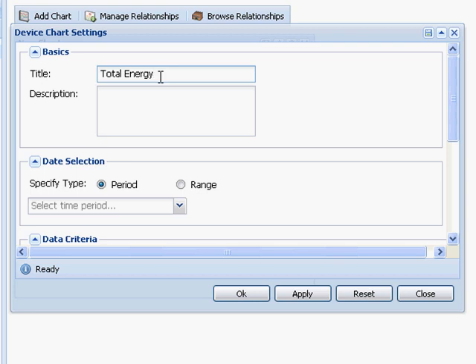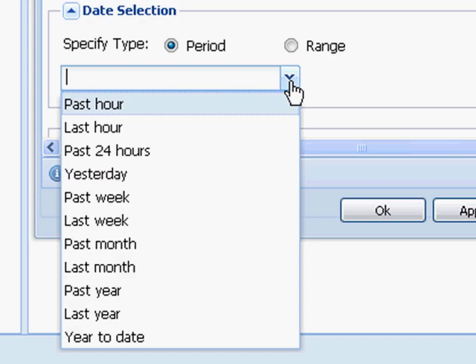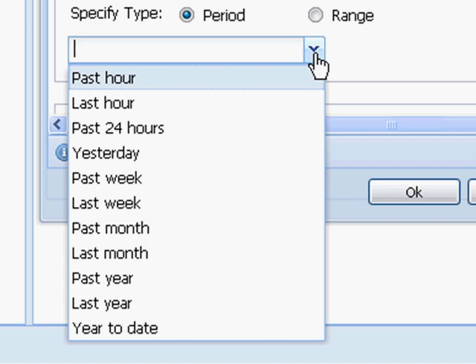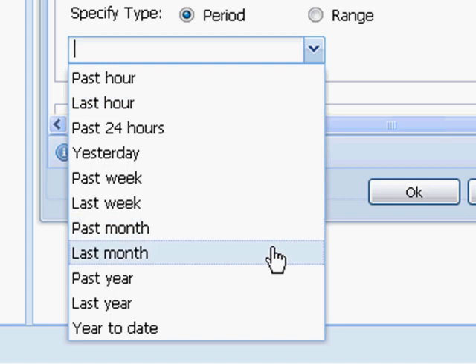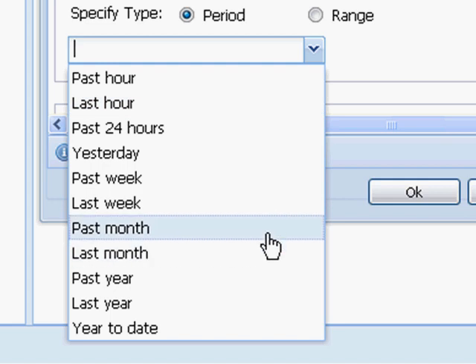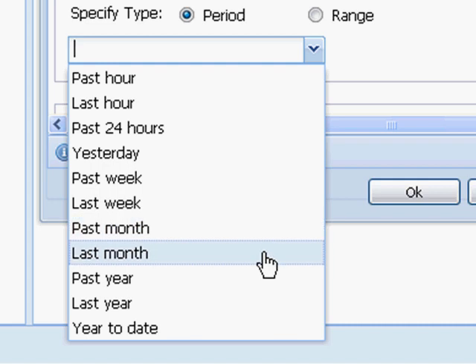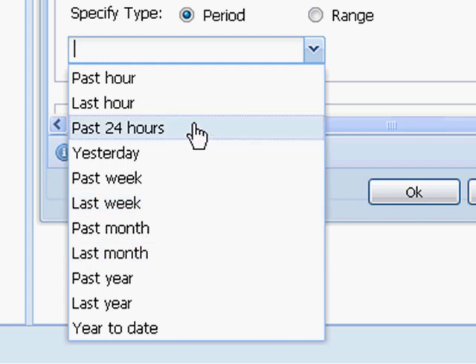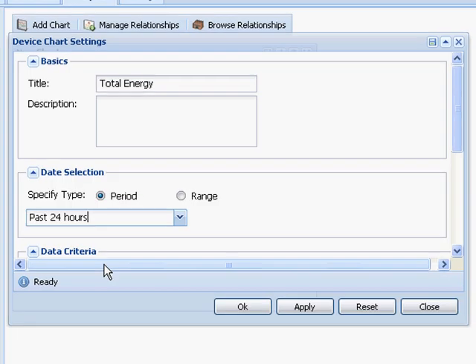I'm going to create a chart that will show the total energy. I can select a number of preset periods from past hour to last month. I'd like to explain the difference between past and last, using month as an example. Past month will chart the previous 30 days. Last month will chart the previous calendar month — for example, it's February, so if I selected last month, it would chart the completed month of January, which is very useful for billback reports. Since this is a total energy report, I'm going to select past 24 hours.